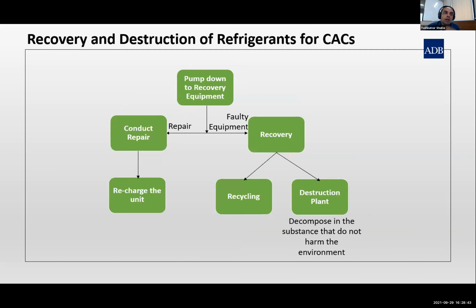Now, talking very briefly about recovery and destruction of refrigerant. There will be times when you have to maintain the system and you will have to pump down the refrigerant. So you pump down the refrigerant to recovery equipment, conduct the repair, and recharge the unit. If the system is repairable, then you recharge the unit and reuse the refrigerant.